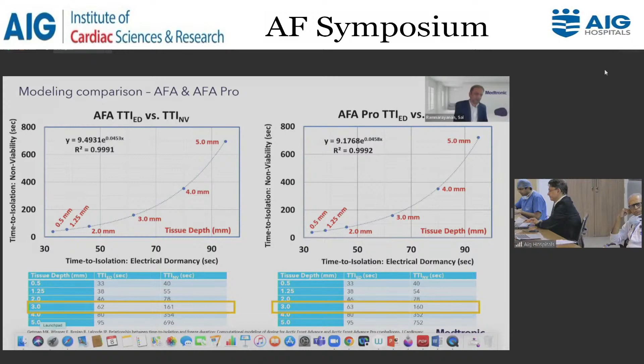So finally, the closing takeaways from this part of the presentation is time to isolation less than 60 seconds is the strongest predictor of durable lesion for cryoablation. Time to isolation is the only real-time marker of circumferential PV isolation. We don't have any others. When time to isolation is not available, there are other strong indicators to guide your ablation, like nadir temperatures. So if you have minus 40 by 60 seconds or a thaw time to 0 seconds, these can be pretty strong indicators that you might have achieved durable PVI.